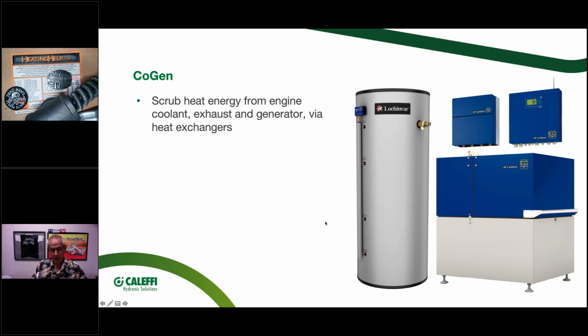When you think about these cogen units, they're thermally led, is the terminology they use. If you don't have a big thermal load all the time, even in the summer, then this doesn't pencil out. To just generate electricity using a diesel or propane fired motor doesn't pencil out unless you have a way to use that thermal energy all the time. You've got to have a big domestic hot water load - maybe a brew pub or something - where almost 24/7 there's a thermal load. That's when the numbers can start to work.